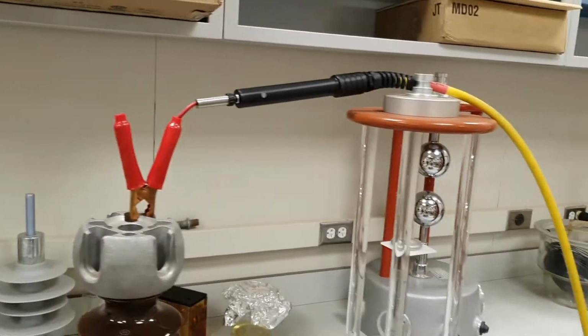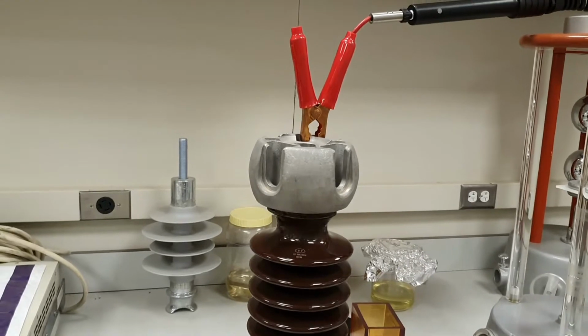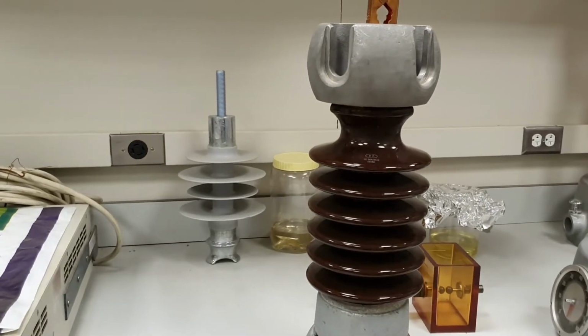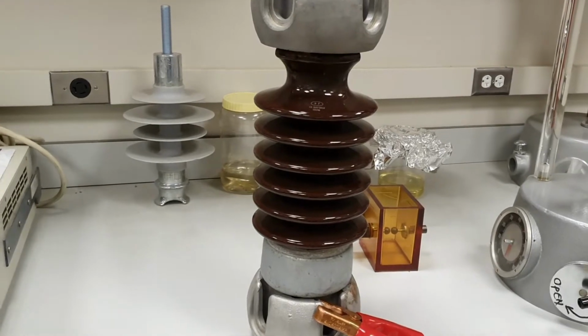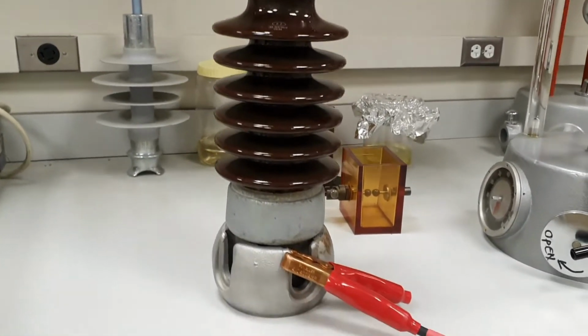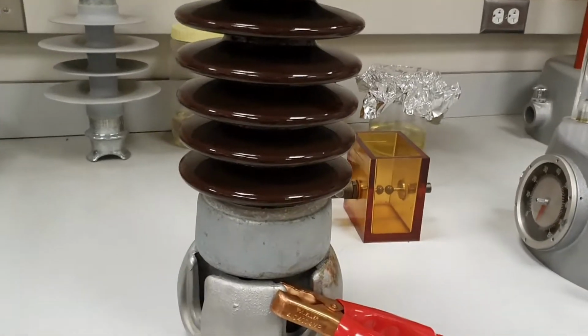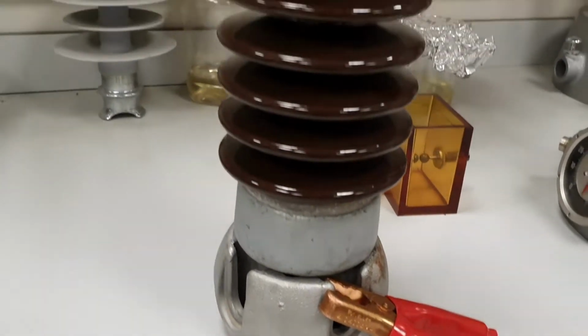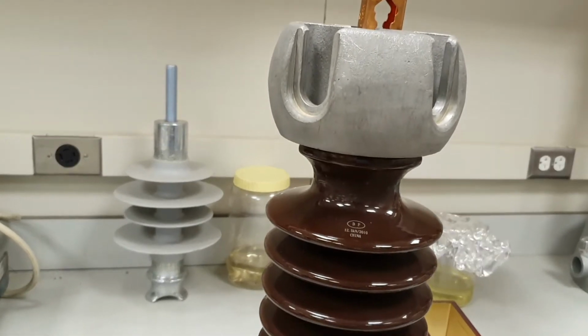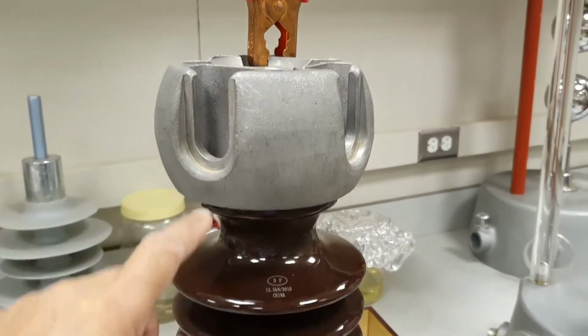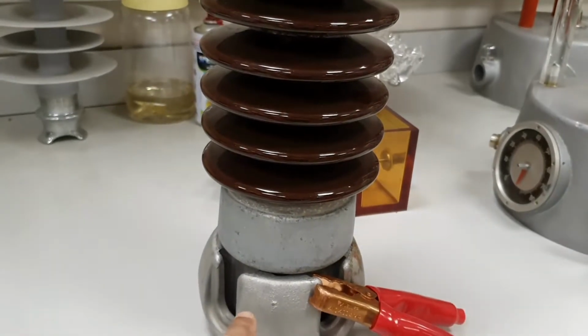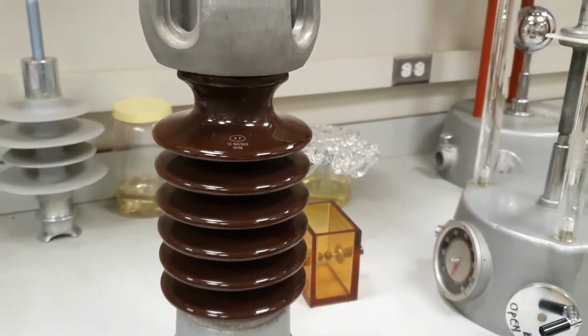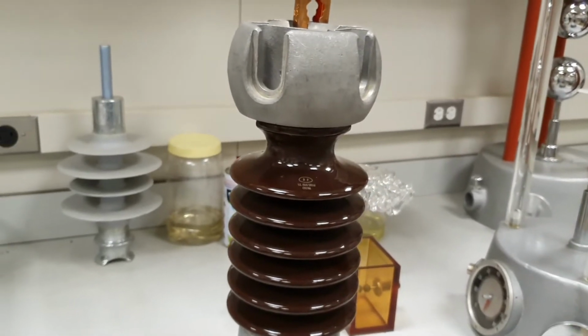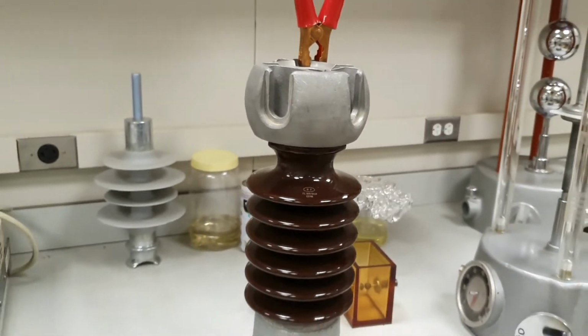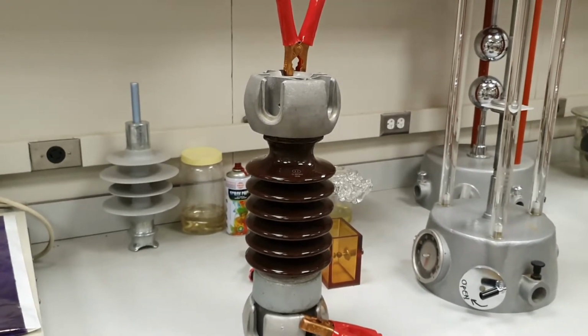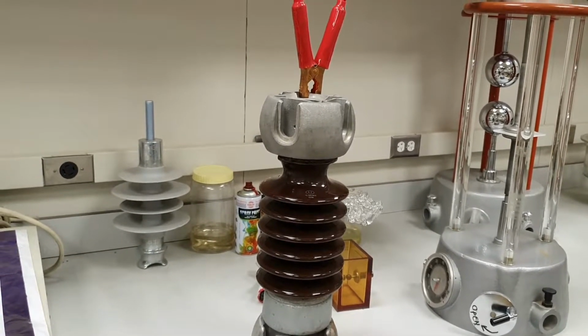This is the high voltage connection coming from the top, connected to the top electrode of the insulator, which is a post ceramic insulator in good, healthy condition with no defects at all. The black wire from the same instrument goes to the ground connection. The insulator sits between two electrodes, one at high voltage on top and the other grounded. This is a clean, dry insulator with no defects, and we'll go back to the instrument to measure the tan delta value again.